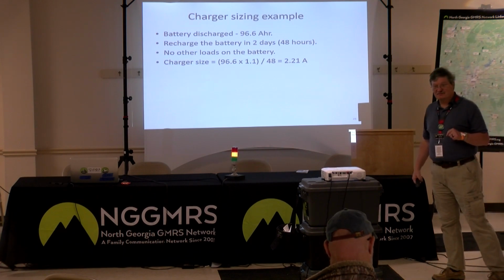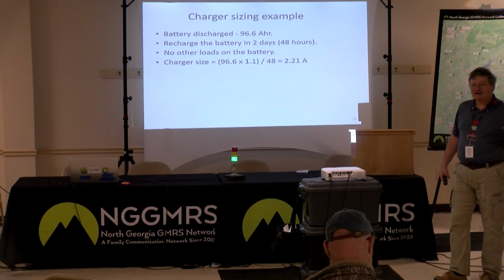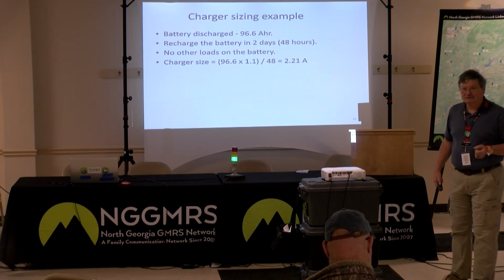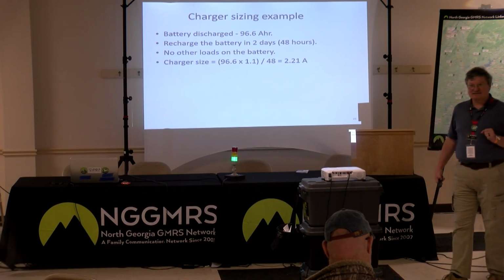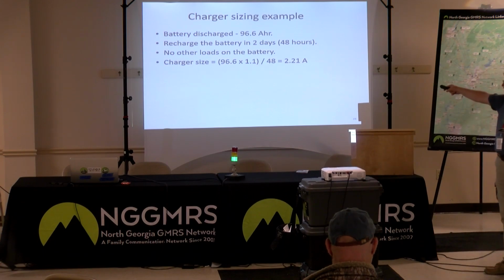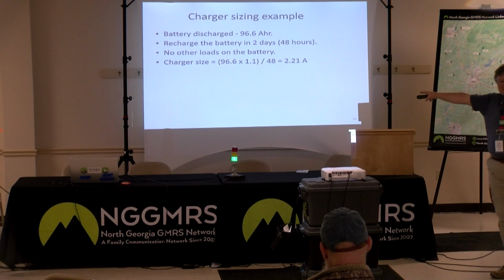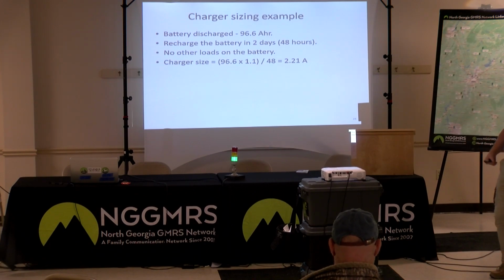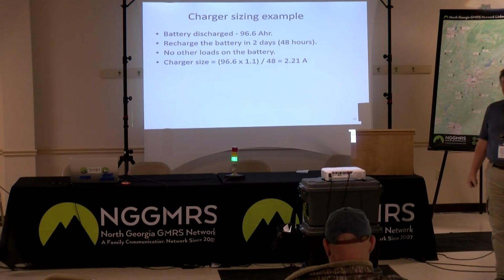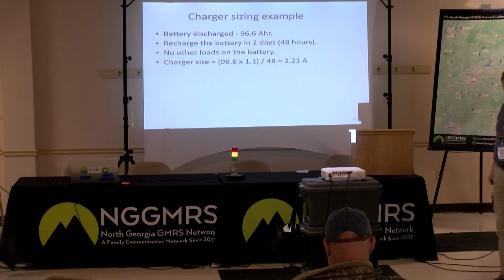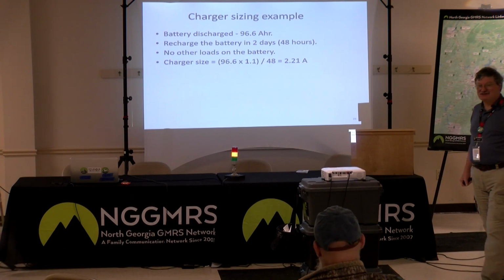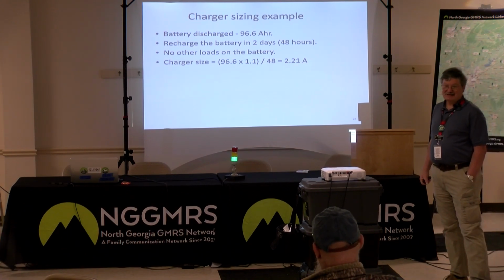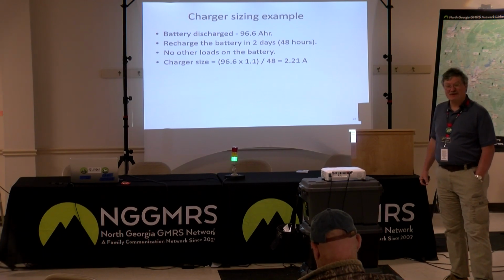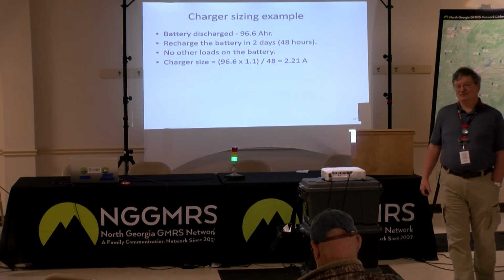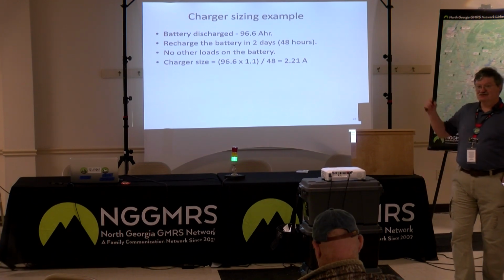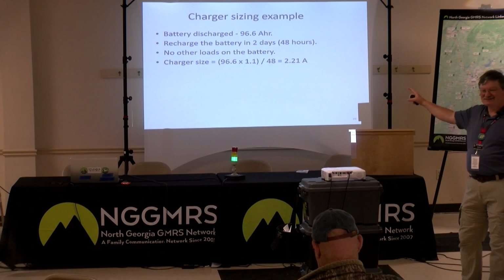I'm saying no other loads on the battery, but if I had other loads, I'd just add it into the current the power supply or charger has to deliver. So on the charger side, I take the ampere hours I need to recharge and multiply that times 1.1. That's a recharge factor that's been used for lead acid batteries for years. It's actually probably closer to 1.06 with newer batteries, but industry has stayed with 1.1. Why? It's close enough.